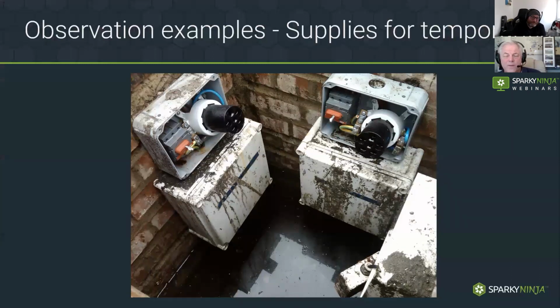We had an earth loop reading of about 0.6 ohms on one and 65 ohms on the other. The old spider sense kicked in - there's something wrong here. When I took the cover off the bottom, it was absolutely rusted to heck.